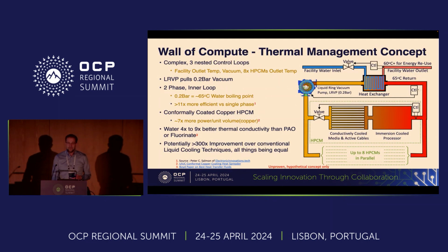Looking at the thermal management side, we've got a really quite complex, crazy idea here that I want to emphasize right at the beginning. This is completely unproven. It's a hypothetical concept, and part of the reason for presenting this is we want all of you thermal experts to be able to tell us where we're going wrong on this. But let me try and explain. In the middle of the diagram on the right, you're actually seeing the high-performance compute module thermal elements. The water passes into that picture on the left, and that gives us a conductive cooling path for the pluggable media and the pluggable active cables. So we actually conductively cool those devices.